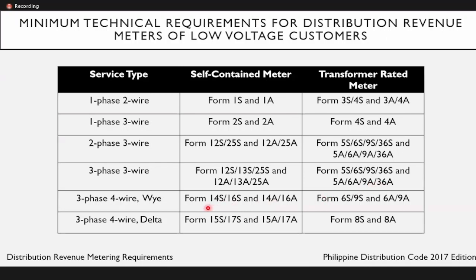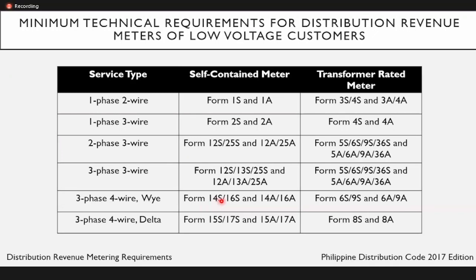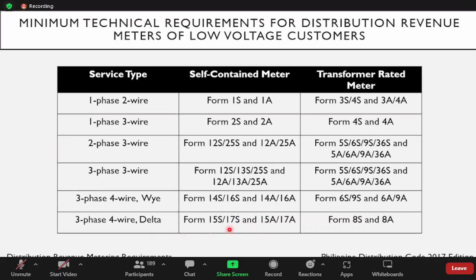For the three-phase four-wire Y, the self-contained meter should be form 14S, 16S, and 14A, 16A. For the transformer rated meter, it should be form 6S, 9S, and 6A, 9A. For the three-phase four-wire delta, the self-contained meter should be form 15S, 17S, and 15A, 17A. For the transformer rated meter, it should be form 8S and 8A.